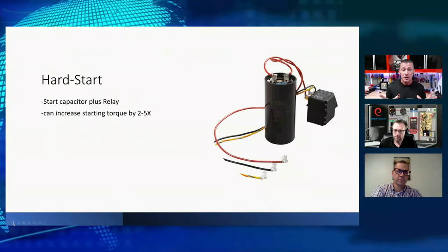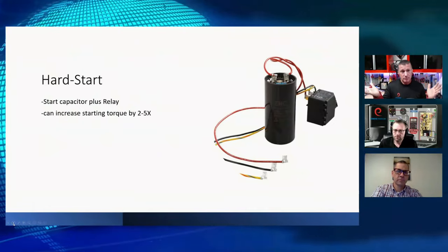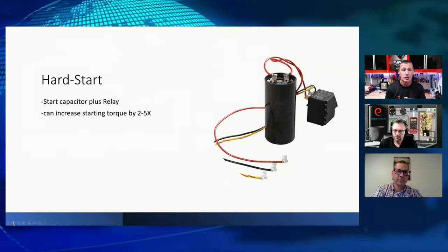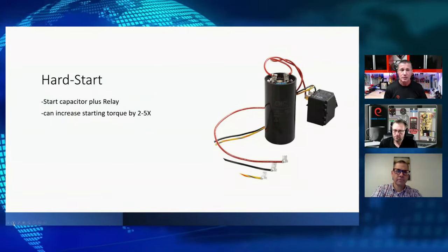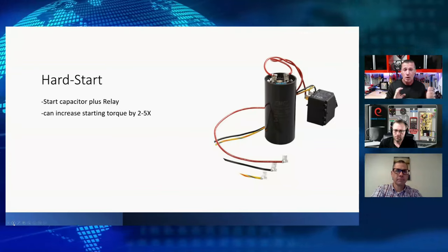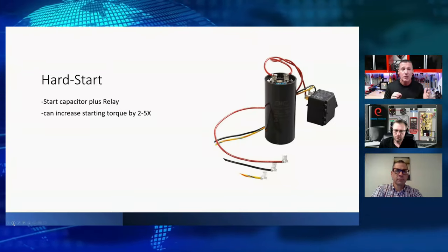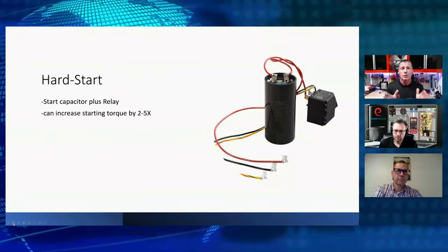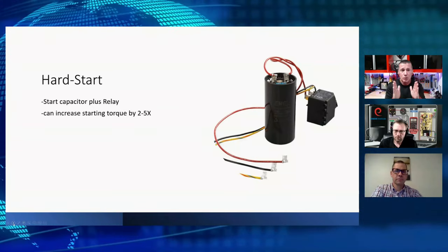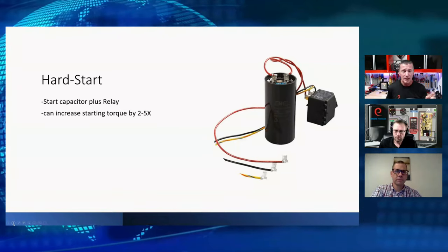Now, we do see some periodically on new installations. It happens, depends on the actual torque rating of the motor inside the compressor. So we're amplifying the torque, not amplifying voltage, just amplifying the available torque for the amount of current we have. We're shortening the window that our current is utilized.